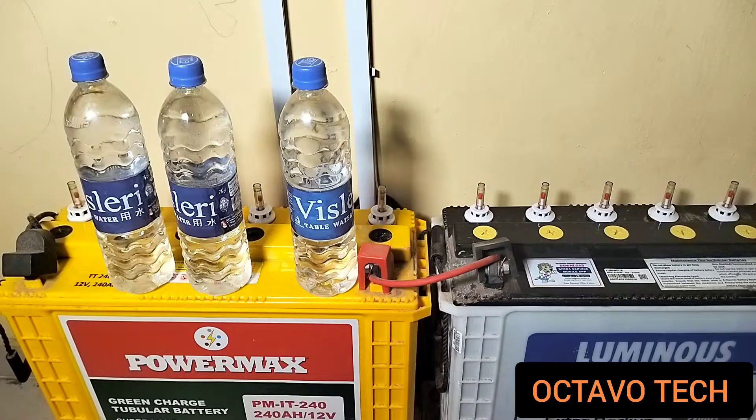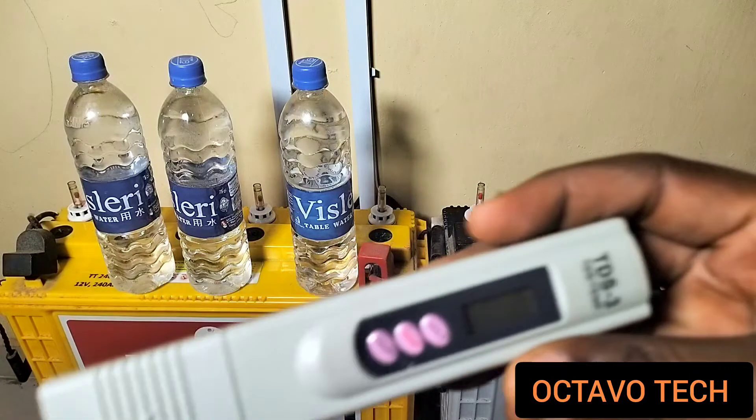This is what I'll be using to top up these batteries. But you can't just use any water randomly — you have to be very sure about the kind of water you are using. If you are using table water, water from a well, or a borehole, you need to check the TDS level. To do that, you need a TDS meter, and here is what a TDS meter looks like.